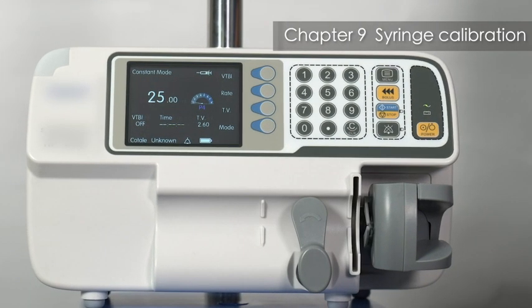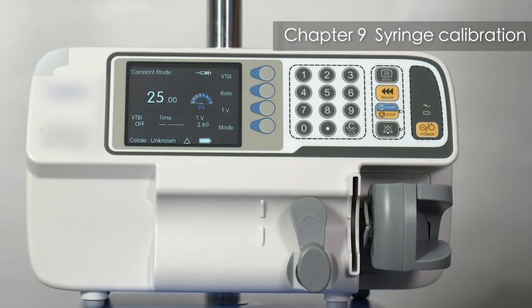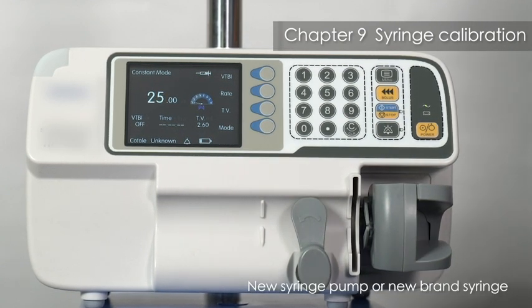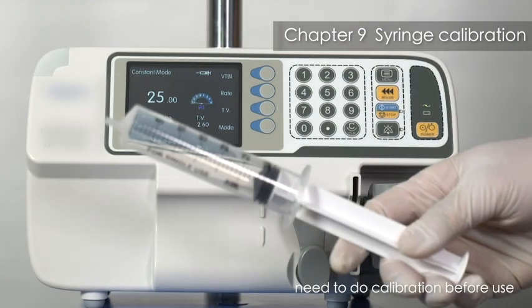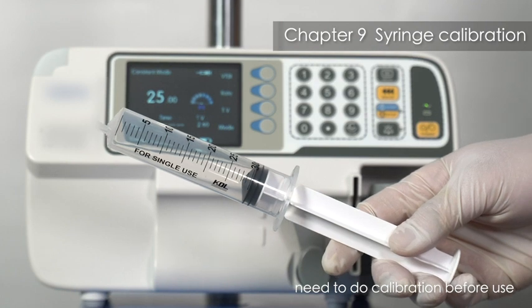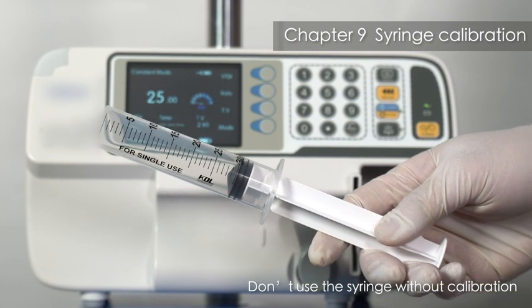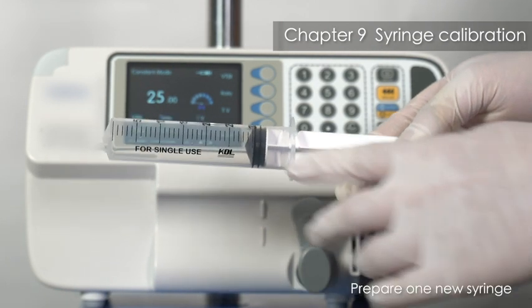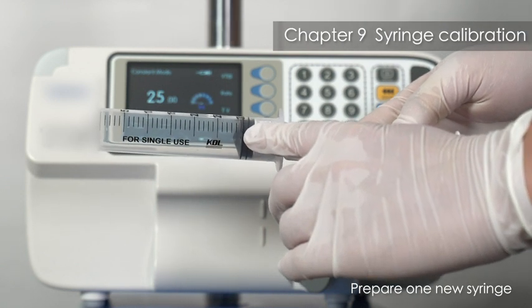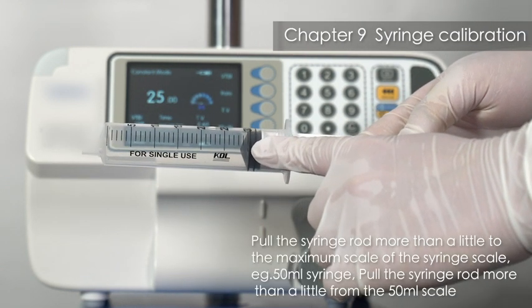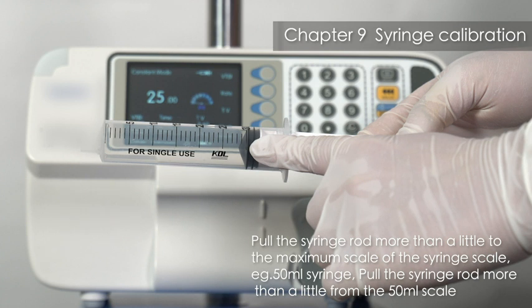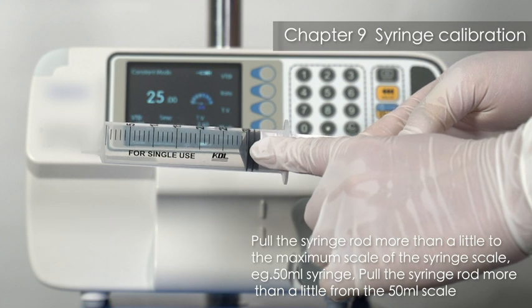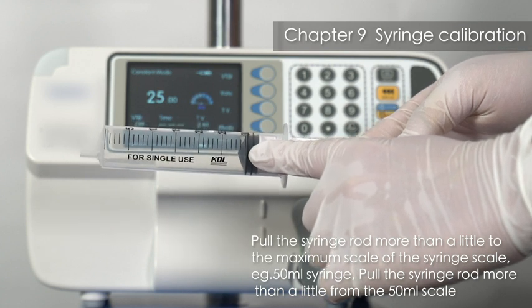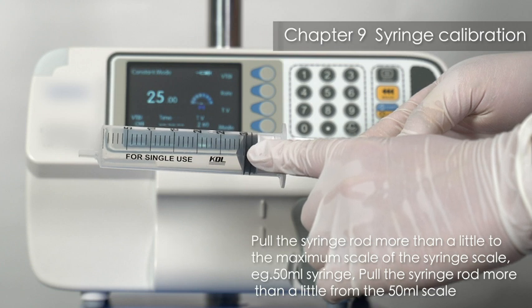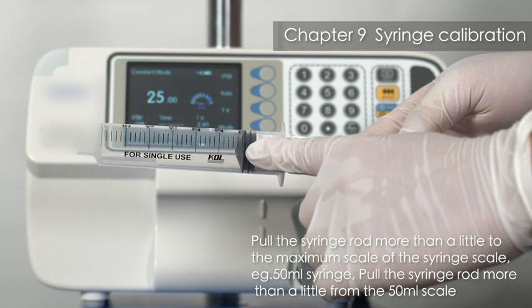Chapter 9. Syringe Calibration. New syringe pump or new brand syringe need to do calibration before use. Don't use the syringe without calibration. Prepare one new syringe. Pull the syringe rod a little more than the maximum scale of the syringe. For example, 50 ml syringe. Pull the syringe rod a little more than the 50 ml scale.